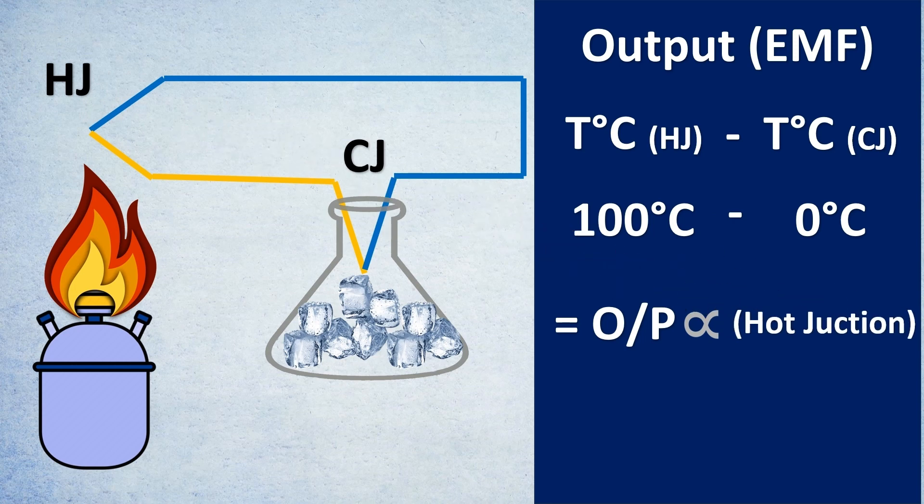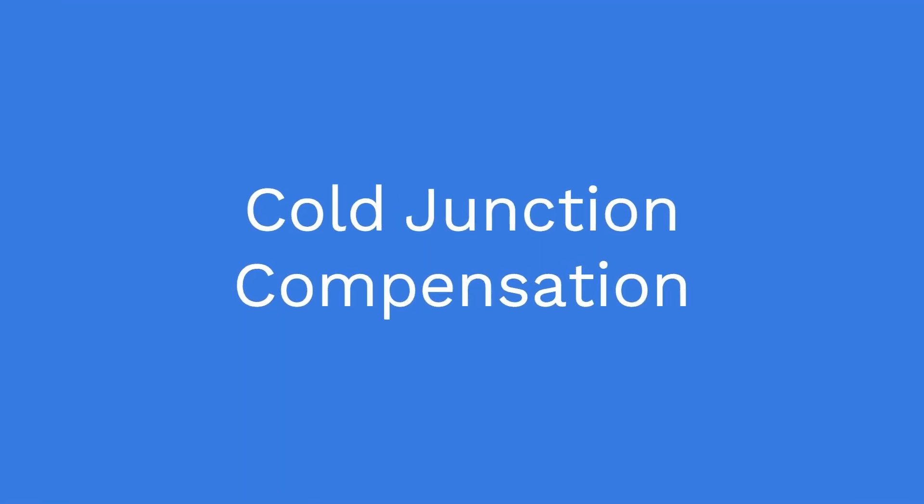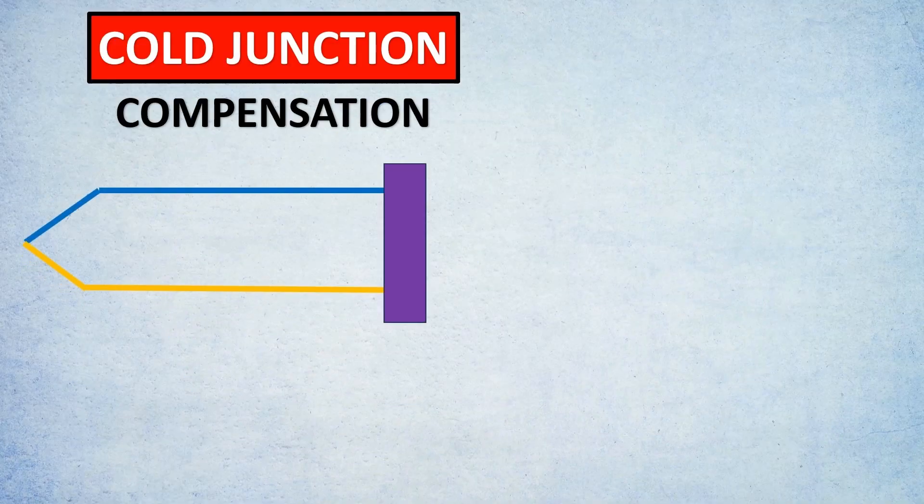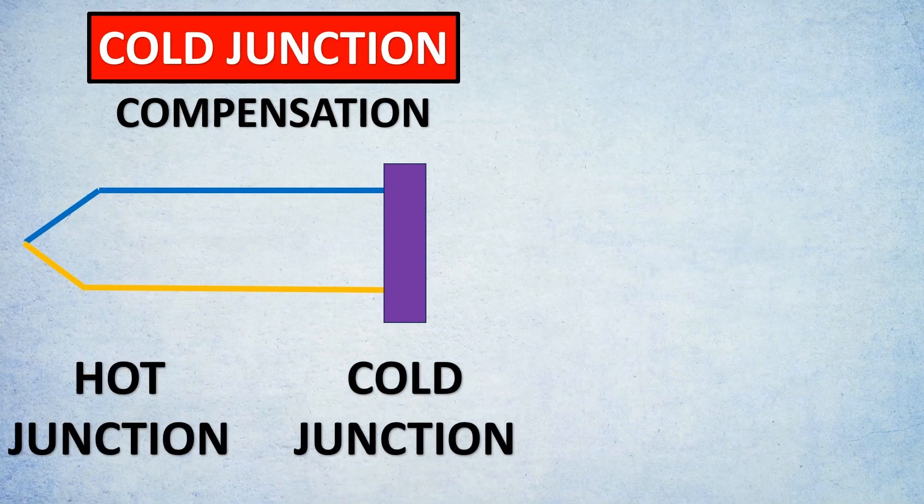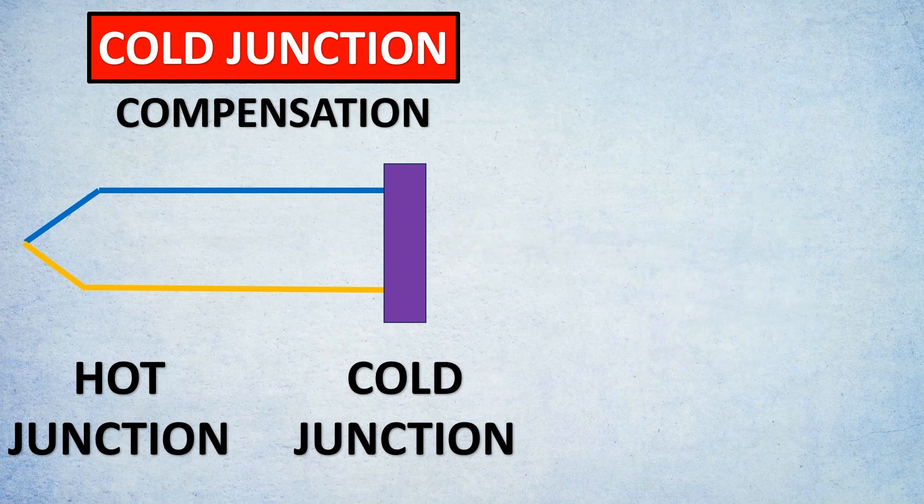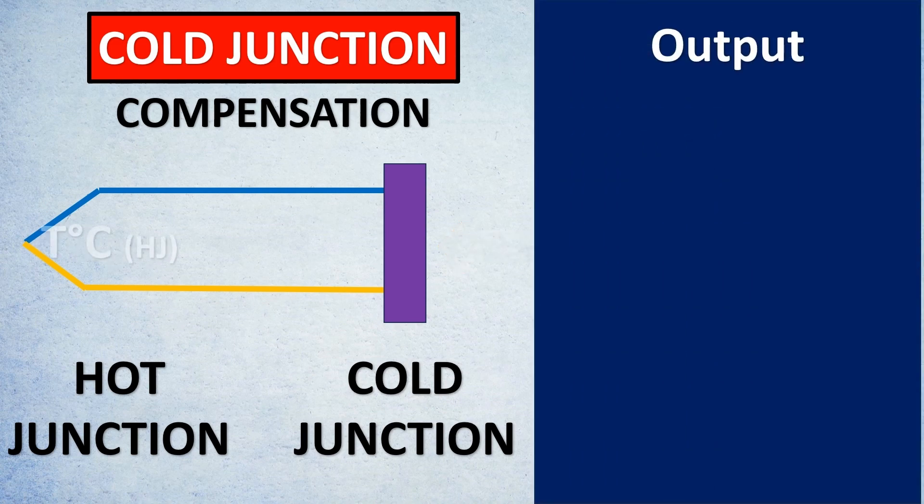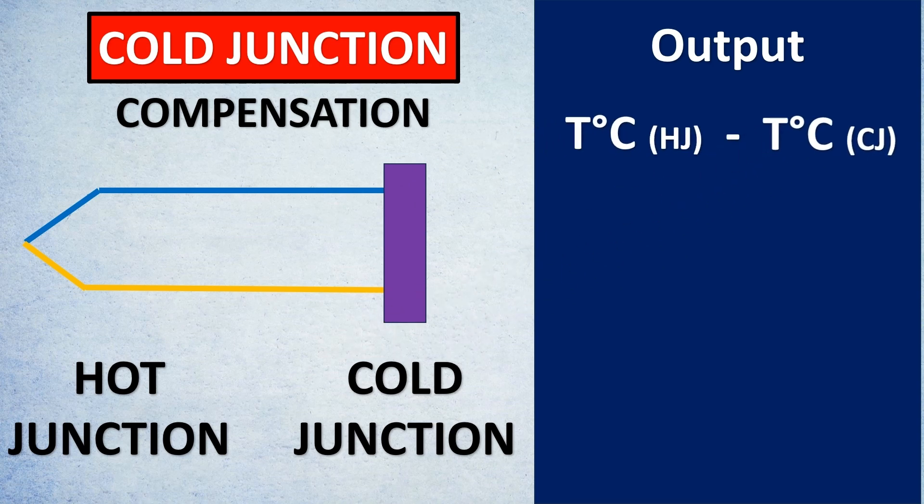But the question arises, what about in industries? So the answer to that is cold junction compensation. So if you look at cold junction compensation, basically imagine that I have two junctions which is the hot junction and cold junction. Now instead of having the ice bath here, what do we do is first we find out the output. What was the output? It is the temperature at the hot junction minus the temperature at the cold junction. The EMF that is generated.